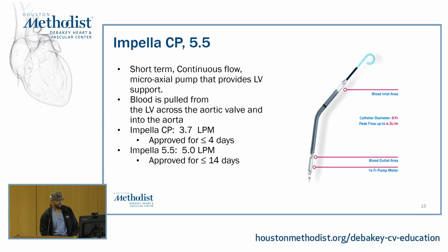It's a short-term device, as I said, microaxial pump. These pumps run at significantly high RPMs, usually potentially 40,000 up to 60,000 RPMs. So when you stay on these devices for a long time, you'll probably start seeing blood trauma. So you might start seeing more hemolysis over time, or other complications associated with that. With the Impella, the blood is pulled from the LV across the aortic valve into the aorta.